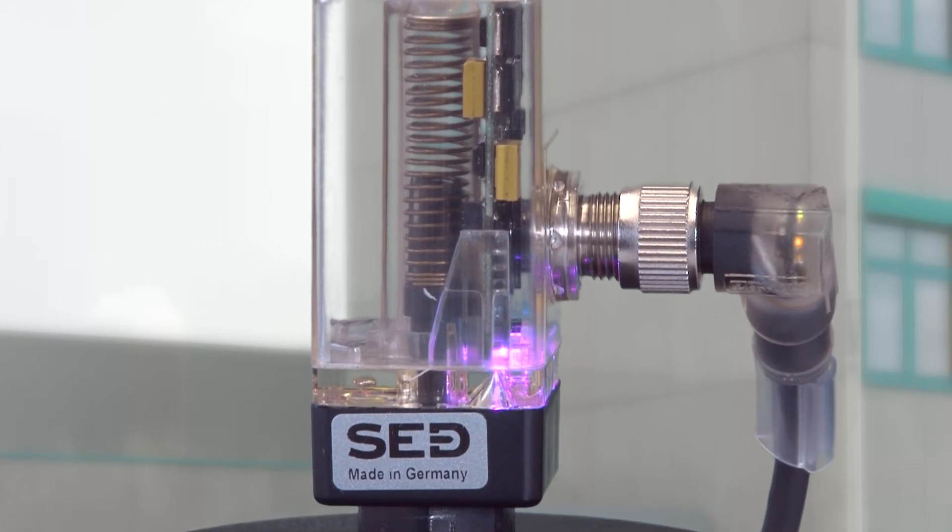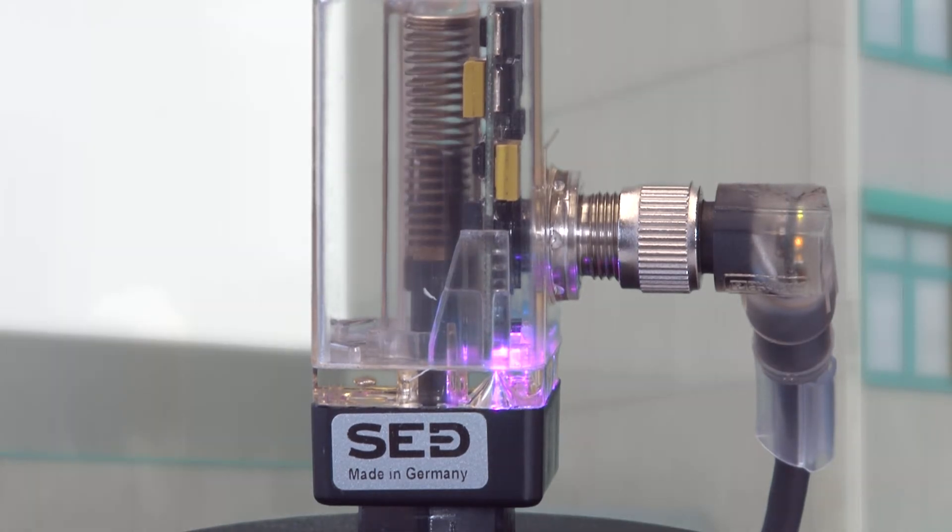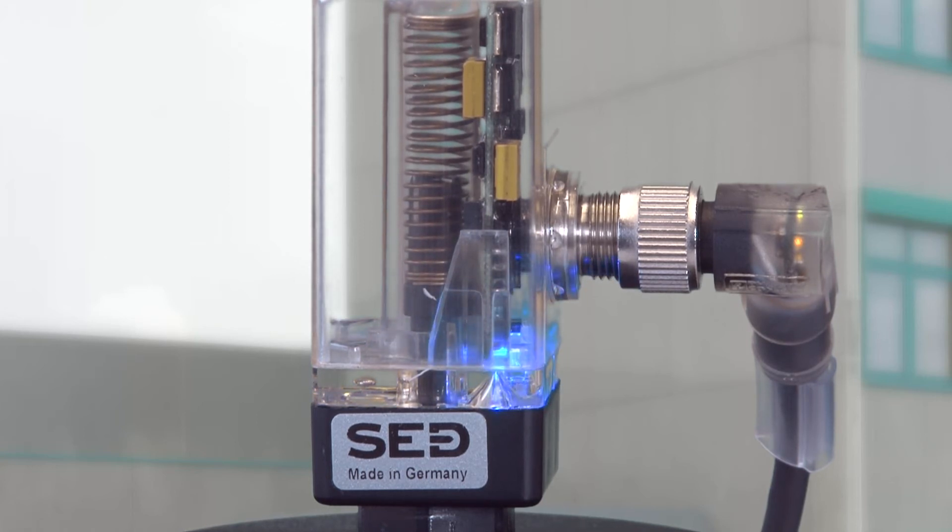Open the valve and hold this position until the LEDs shine permanently violet. Close the valve to finish the programming. The end of the programming is indicated by a change in colors. The electrical limit switch shines blue and is now ready for use.